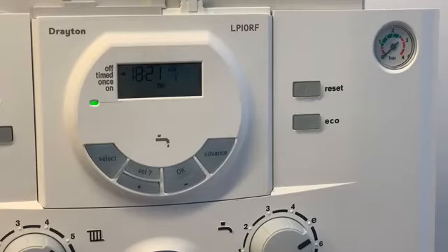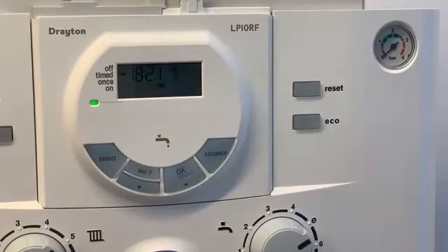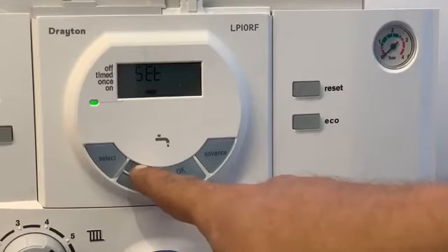So the way we commission this, so this is an LP10RF. So we looked last week at the clip-ins. This is the RF version of the clip-ins. It comes with, you can get it with a Digistat +2 or +3 RF. So the way you commission these is, first thing is you start with the batteries out of your control. So you want to start with the control powered down. You press and hold the set button and you keep it held in.